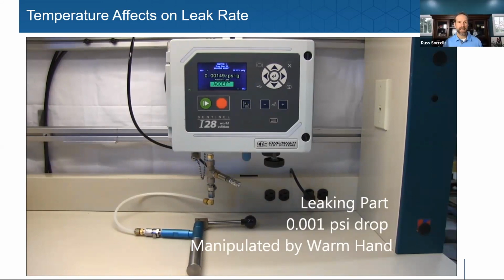Yeah, and something to emphasize, and I will beat this horse, is that it is pressure change that we are worried about. And so all of these things that we're talking about affect the pressure, because that's what we're measuring with all of these tests is pressure change. Even with mass flow, we're measuring pressure change utilizing flow technology.